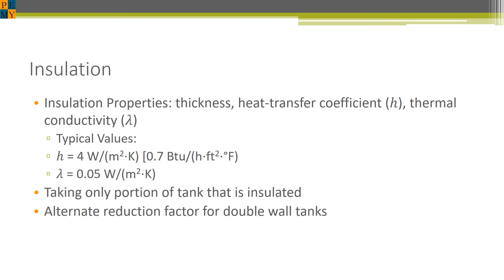When considering insulation, this depends on the thickness of the insulation as well as properties like the heat transfer coefficient or the thermal conductivity. API 2000 lists typical values that can be used for these different parameters. Only a portion of the tank surface area is actually used to determine how much credit can be gained from insulation. It's the portion of the tank that's actually insulated. You take a ratio of the insulated portion to the total surface area of the tank, and that's how much you can account for insulation. An alternate reduction factor is found for double-wall tanks where the second wall can be considered a form of insulation as well.